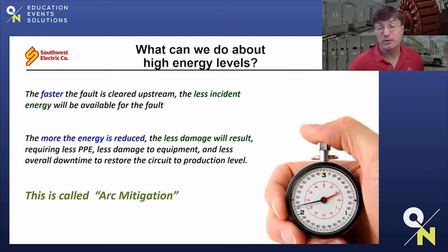But there's one more critical area I would like us to focus on. That's mitigation of this arc flash energy. You have all these high energy levels. What do you do about it? You don't really have to live with it. Most of the time, there are methods and capabilities to reduce this energy level and allow greater safety for your personnel. That first line on this slide is extremely important. The faster you can clear an arc fault upstream, the less incident energy you're going to see at your equipment level. And we saw that in the arc table just a few slides earlier. So the more energy that's reduced, the less damage you have to the equipment, certainly the less risk you have to personnel, and then you have less downtime for your equipment to be restored so you can resume production.